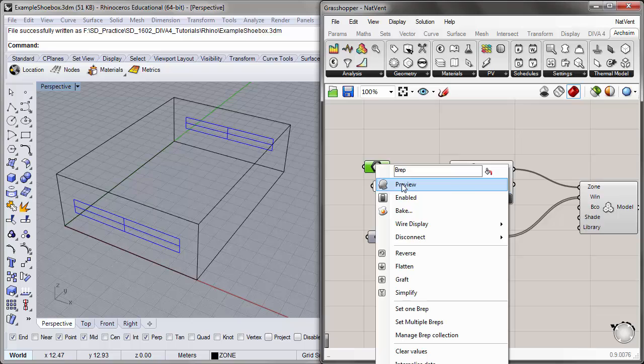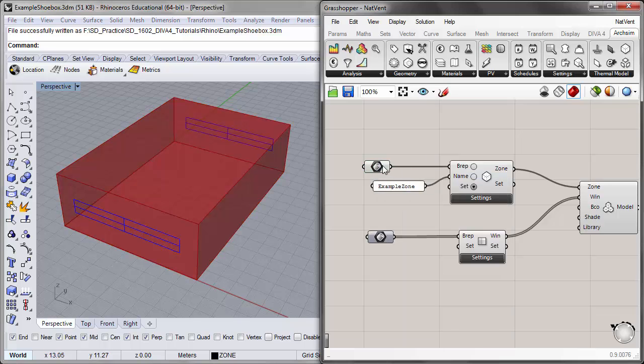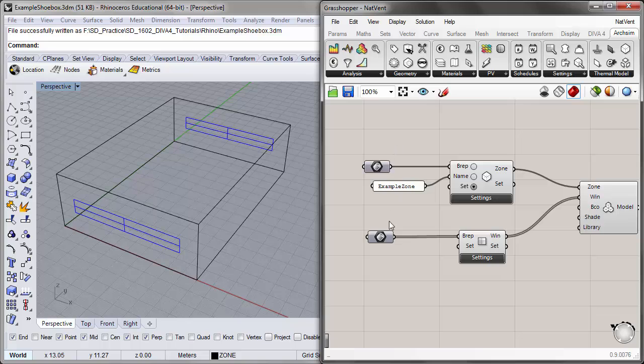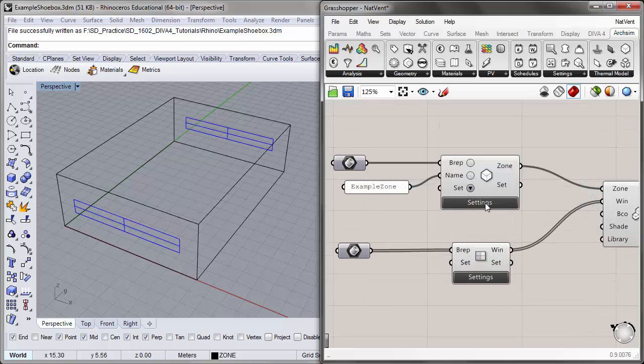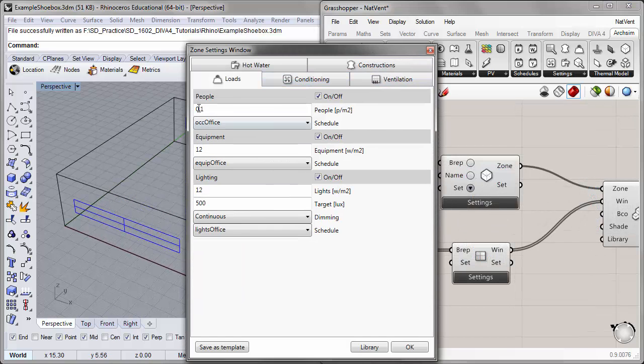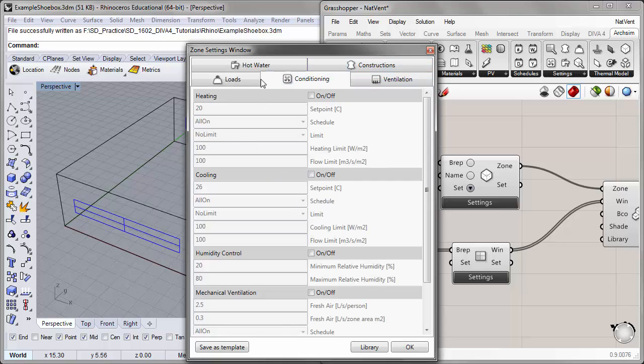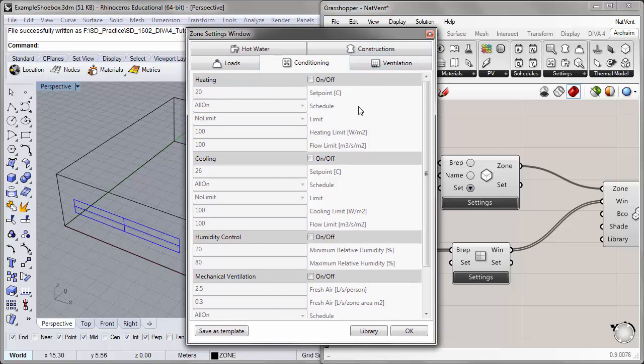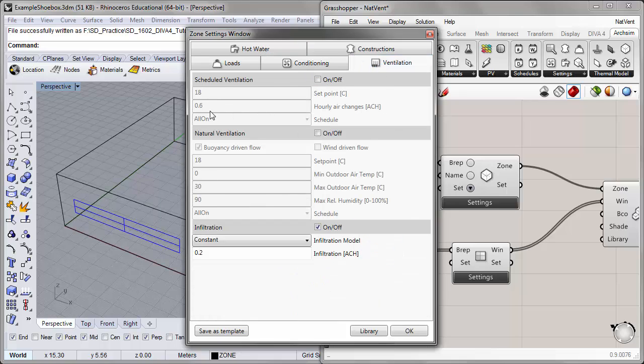I'll zoom in here — we have the thermal zone assigned to our BREP, which is input in the thermal zone component. I'll turn the preview back off. I'll go ahead and turn on the settings for the thermal zone. I will leave the loads the same as before — people, equipment, and lighting. Under conditioning, I want to make sure that heating and cooling are turned off, because I want to run a simulation on the hourly temperature profile without any heating or cooling loads. Under ventilation, I'll make sure that natural ventilation is turned off, because I'm going to run an analysis on the baseline without any ventilation.